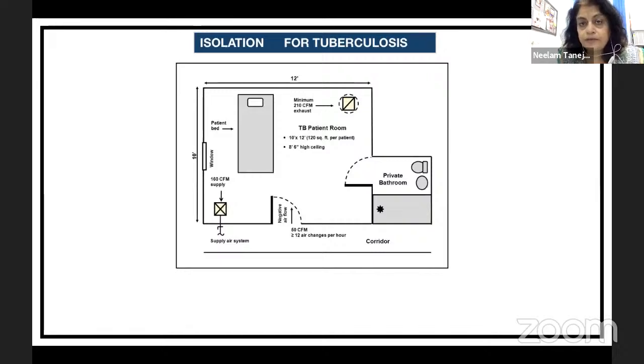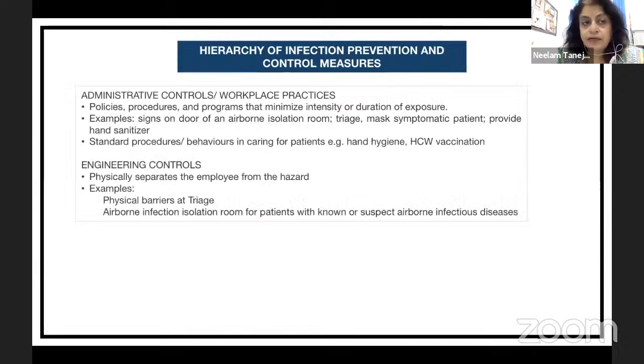How do you make isolation for tuberculosis? You could have, again, a negative isolation room for tuberculosis. And this is the pressure differential. This is the 160 cubic feet supply of air, and this is the exhaust mode. But if you don't have negative pressure for tuberculosis, you would just have a no pressure room with sufficient cross ventilation and preferably some sunlight, like used to happen in the sanatorium.